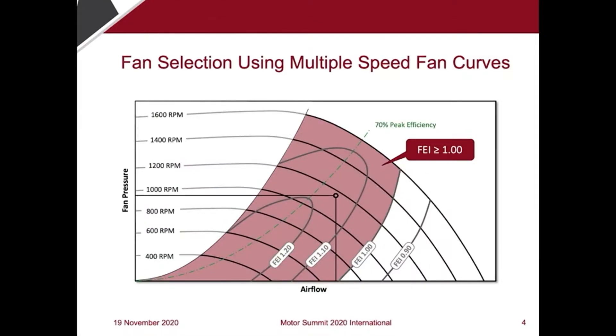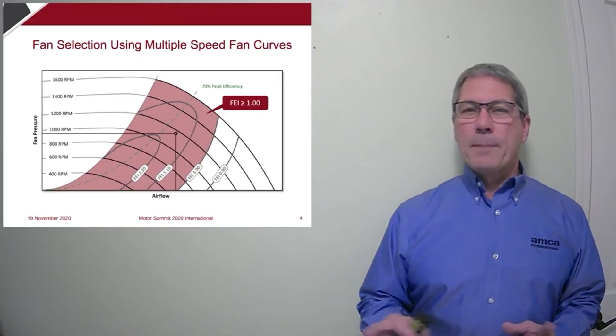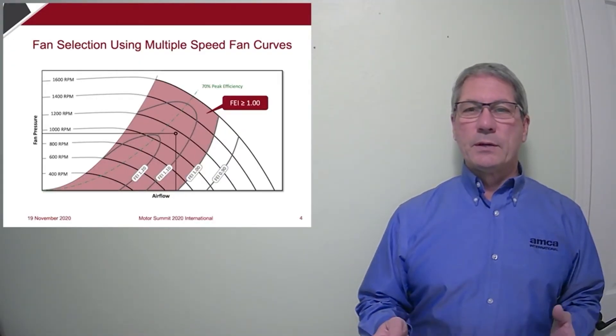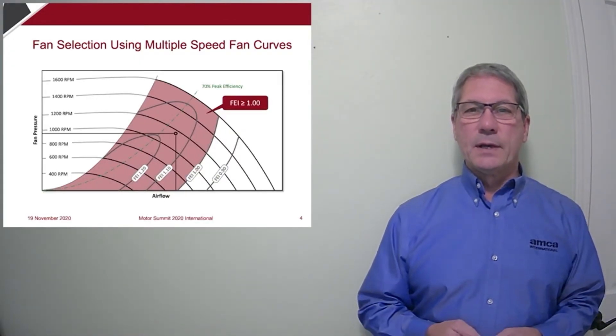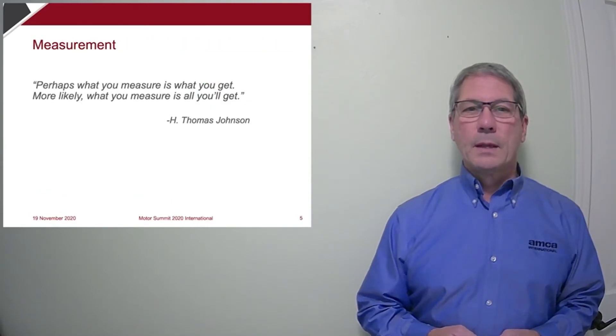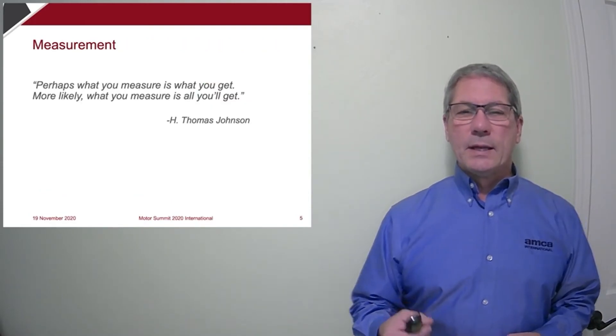But what makes FEI unique from other energy efficiency metrics is that it can be calculated at any duty point. Any airflow and pressure point within the fan's operating range. It's not just a single metric applied to a fan model. So if the fan is available at multiple speeds like this one, there's a whole map of FEI values shown here as lines of constant FEI.